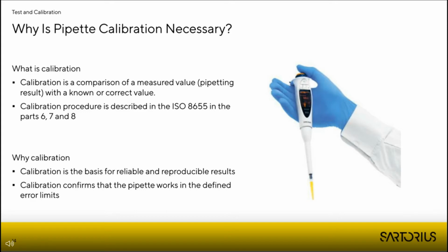But let's start with some basics. What does calibration mean, and why is calibration of a pipette necessary at all? Each pipette, independent of whether it's a mechanical or an electronic pipette, and independent of the pipette manufacturer and the pipette model, has a small error. This means if you select, for example, a volume of 300 microliter, you will never get exactly this 300 microliter dispensed. It can be a very small deviation, but there will always be a small error.